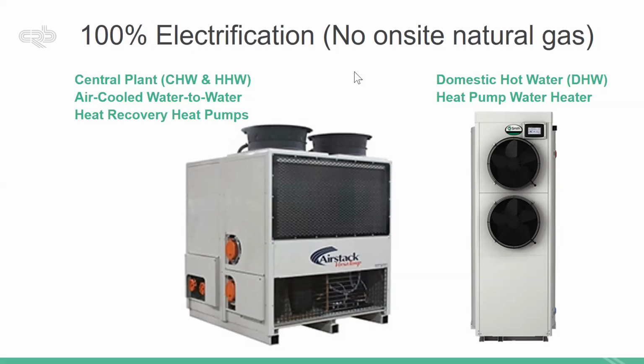What you're seeing on the screen is, it's a mouthful, an air-cooled water heat recovery heat pump. It looks like an air-cooled chiller, and essentially, when there's no heating, it is. There are 4 pipes on the side - these are your chilled water, larger pipes. However, there's another heat exchanger that allows that heat, rather than being rejected to atmosphere, to be rejected to your condenser barrel and actually create heating hot water.